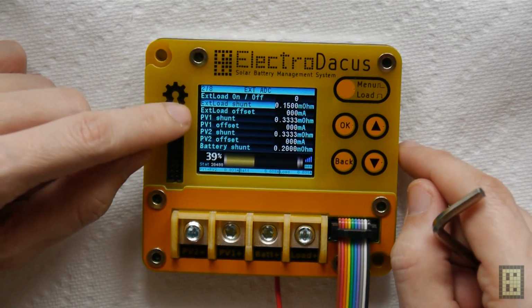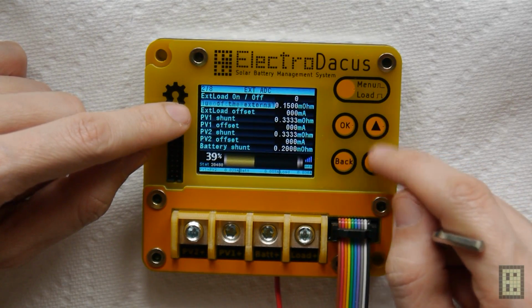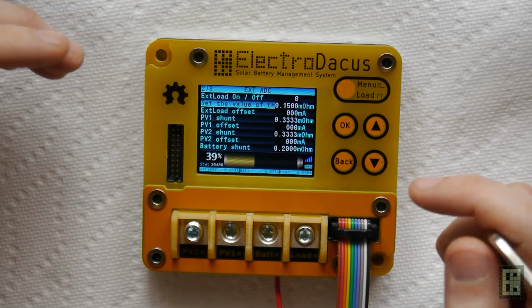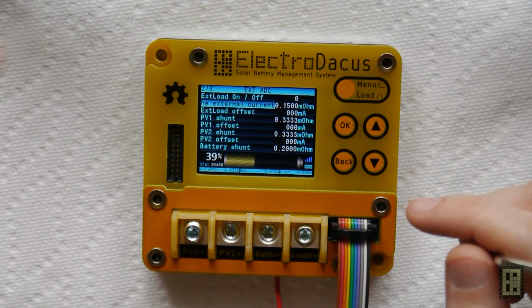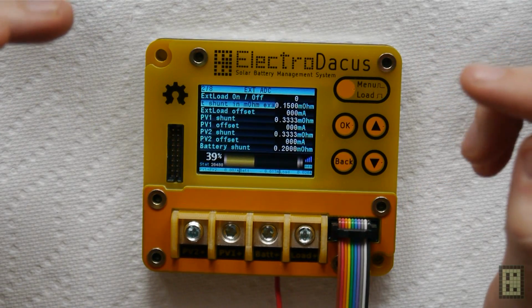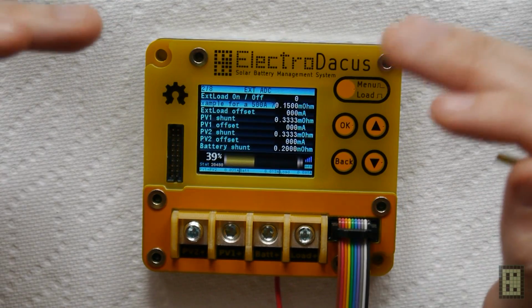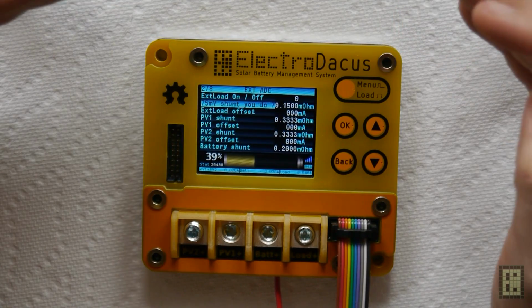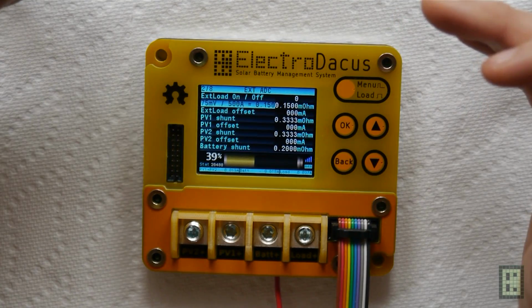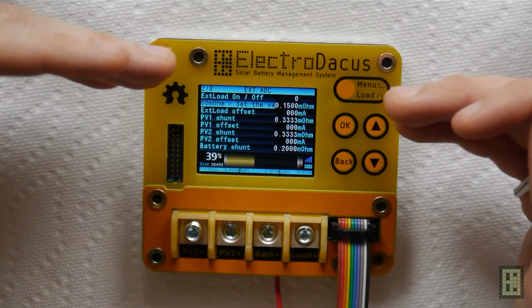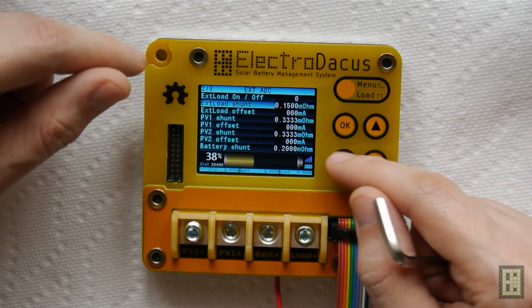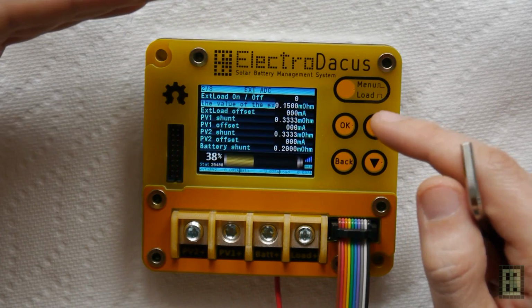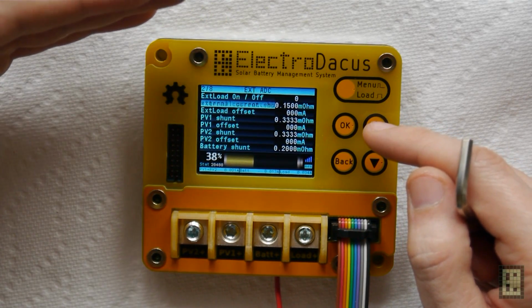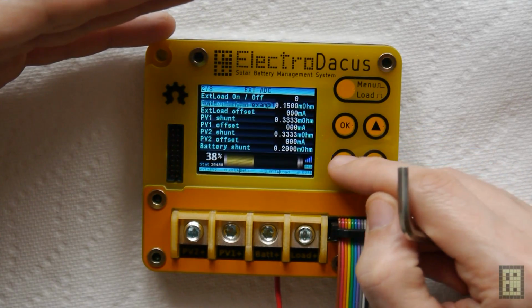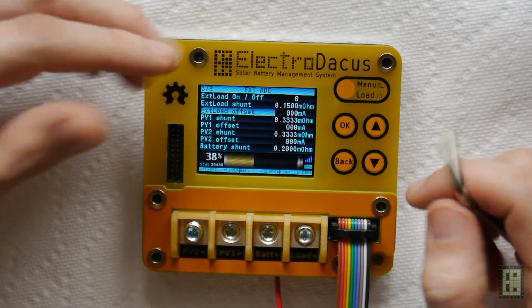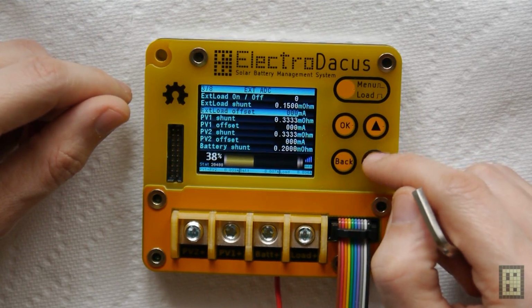Then you select the external current shunt value. To do that, you divide the output voltage rating of the current shunt, usually 75 millivolts, by the current rating, and you get a resistance value to enter here. This example is already set for a 500 amp, 75 millivolt current shunt.